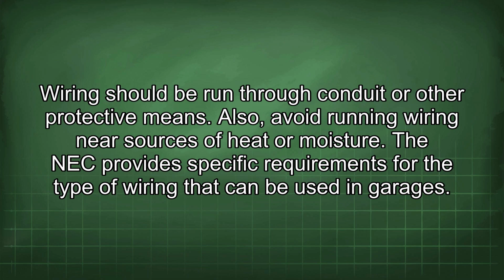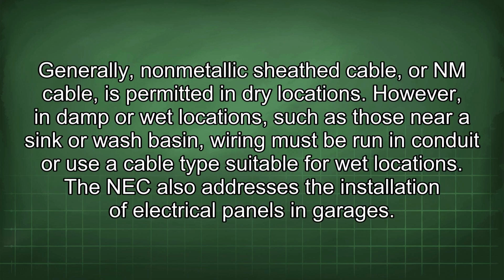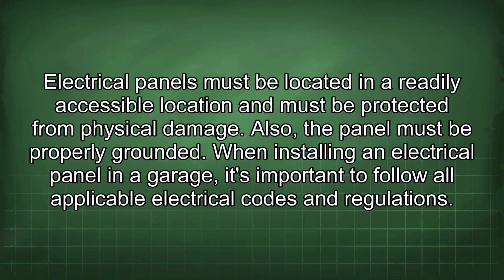The NEC provides specific requirements for the type of wiring that can be used in garages. Generally, non-metallic sheathed cable, or NM cable, is permitted in dry locations. However, in damp or wet locations, such as those near a sink or wash basin, wiring must be run in conduit or use a cable type suitable for wet locations. The NEC also addresses the installation of electrical panels in garages. Electrical panels must be located in a readily accessible location and must be protected from physical damage. Also, the panel must be properly grounded.